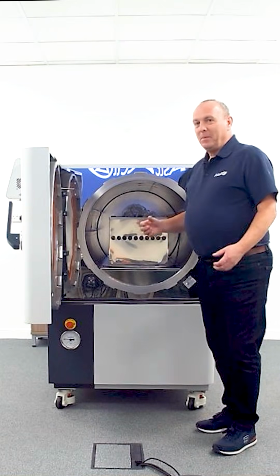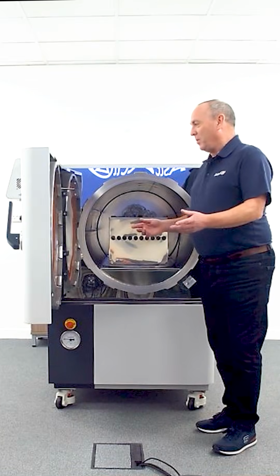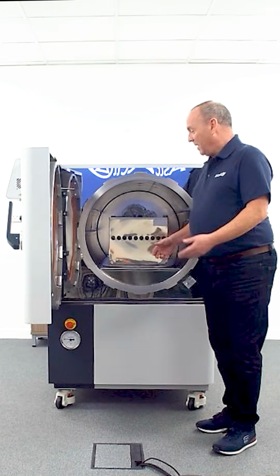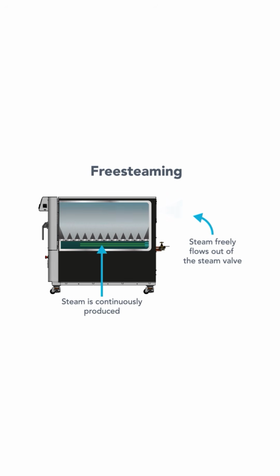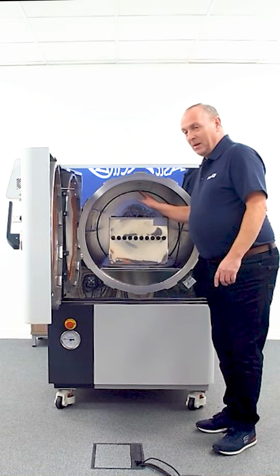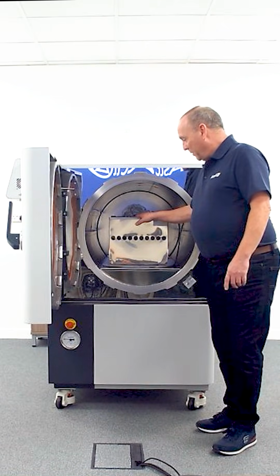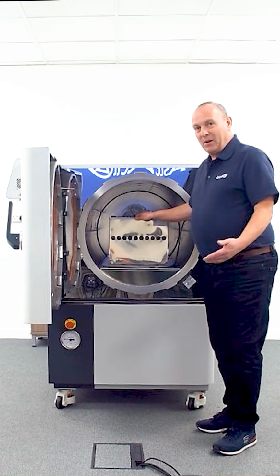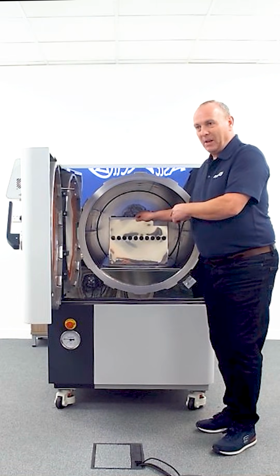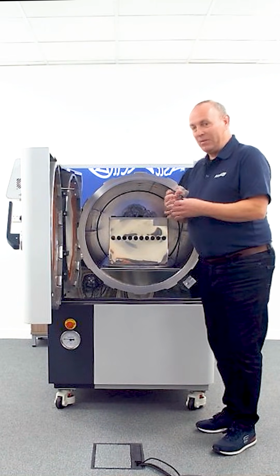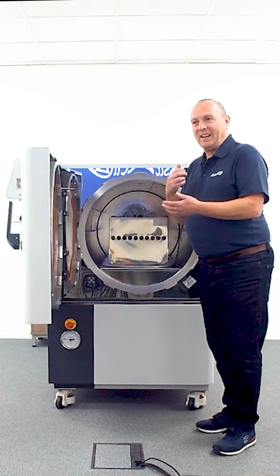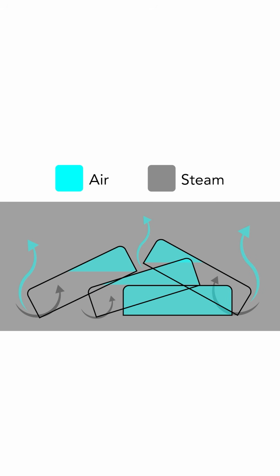For a discard cycle, we have the same procedure. The door would shut, you just press the start button obviously. The machine would heat up, being self-generated, it would produce steam and then it would free-flow steam, normally again at 95 to 100 degrees, for a period of time to allow the load to catch up with the chamber temperature. And obviously what we're trying to do under free-flowing steam is get rid of the air out of the load. The Petri dishes have air pockets, everything will have air. The art of sterilisation is to get that air out of the load. So the load will then warm up and sterilise.